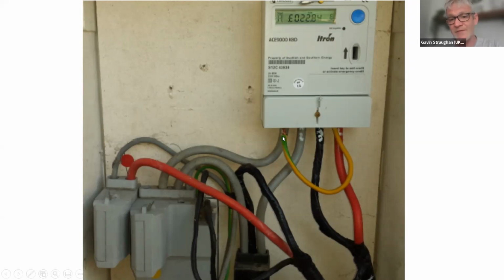Now, we have exposed parts here. This is exposed copper. So you touch that and you're likely to lose an arm, or if not your life, or at least start a fire. This is how dangerous this is. So if you see anything, there are other telltale signs on here as well, such as the seal is missing on the meter, and also that meter terminal cover is actually upside down. But they're little things that we wouldn't always expect you to spot.